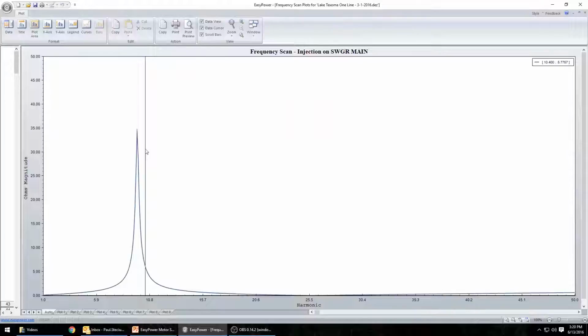If I double click the bus, you can see that now I have a resonant point down in the 9.7th range. The soft start is going to be putting out harmonic currents at the 5th, 7th, 11th, 13th and 19th harmonics. So in this situation, we're at 9.6 here. If I was to scroll over to the 11th harmonic, you can see that at this point there is some magnification of voltage distortion, but not too bad.